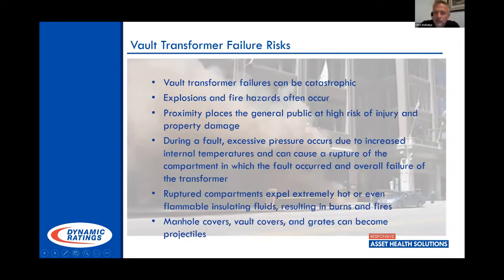These vault failures can be catastrophic. Towards the end of my career, maybe once every other year, we would have a catastrophic failure of one of these, resulting in some type of fire in the vault. Also, there's quite a bit of explosion associated. If you want to go through YouTube and take a look at these, there's plenty of videos, especially of that cable compartment, being such a small compartment, holds about 8 gallons of oil. When that explodes, you're trying to contain that arc flash in a very small compartment. So it's really an impressive thing to see when one of them goes up.